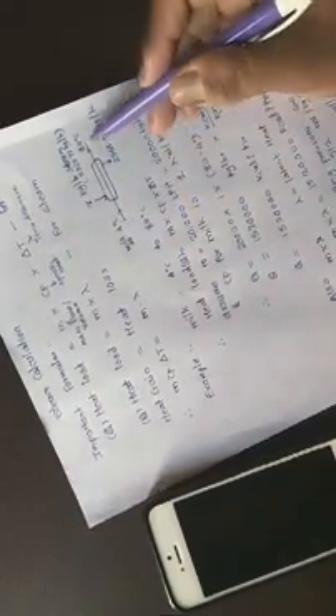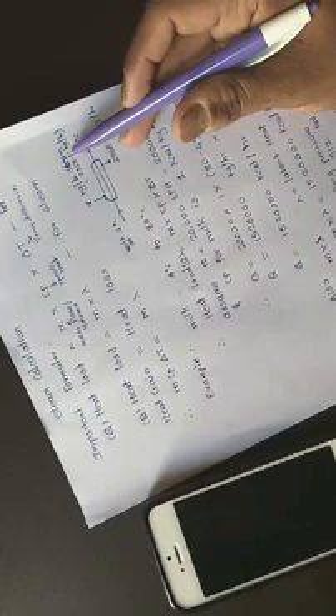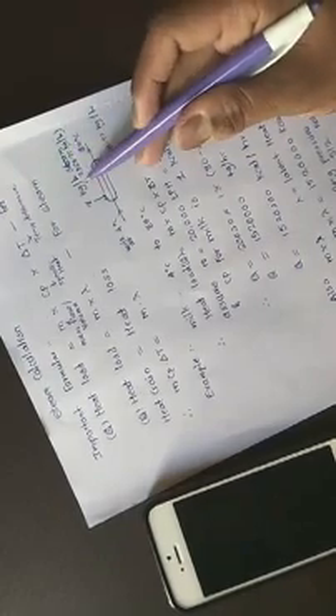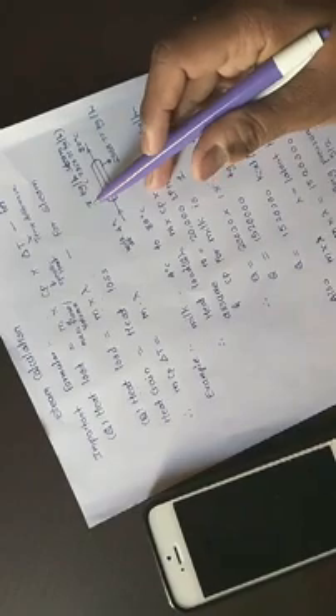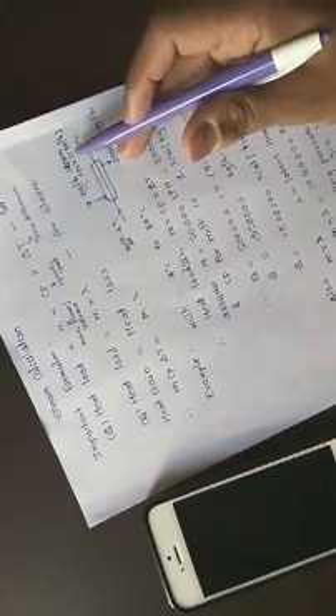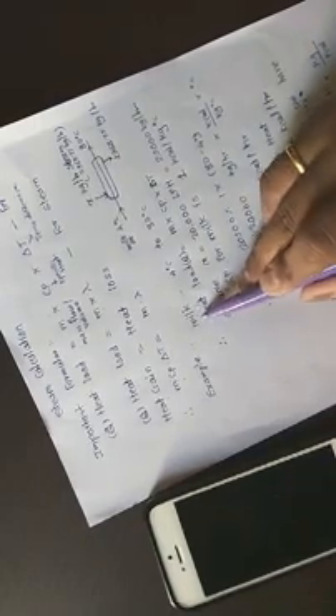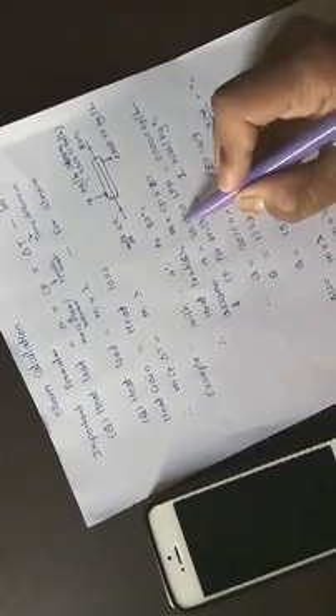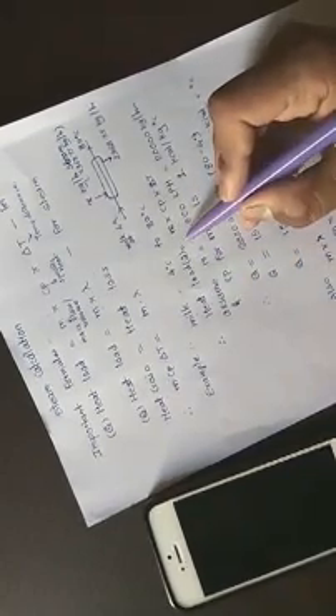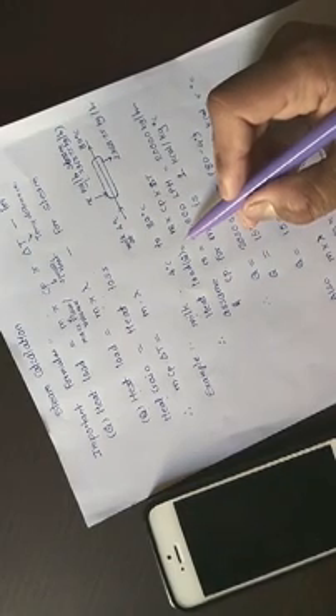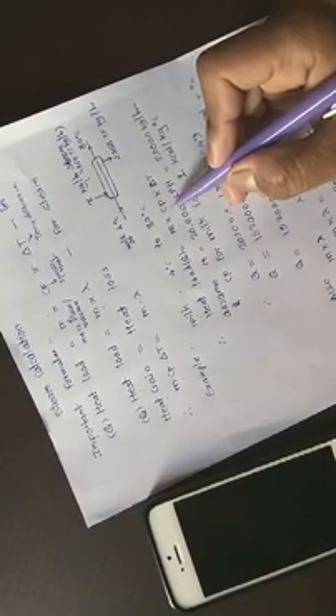So I want to heat milk from 4 degree Celsius to 80 degree Celsius. I don't know the steam flow rate. I have calculated this, but at this moment you don't have this figure. So x kg per hour of steam is required. So my basic duty is to heat milk from 4 degree to 80 degree Celsius. So heat load from product side will be M into Cp into delta T. For heat load calculation, you should know your milk flow rate in your line, whether it is the pasteurizer or thermizer. Cp you will get from the internet.